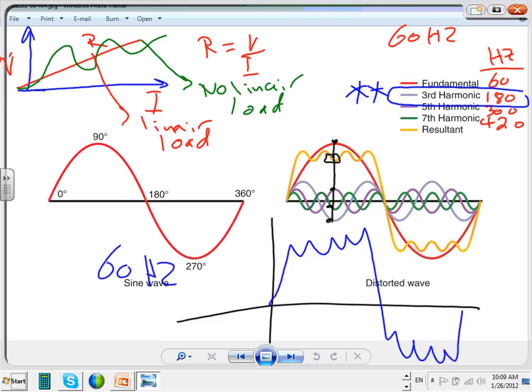Third harmonic is the opposite of that. You have 10, 10, 10. On the neutral, what do you get? 30. Who cares? The question is always who cares? Well, you're going to burn the neutral. So don't derate. Then we get into not derating the neutral because of that, or having a larger neutral.